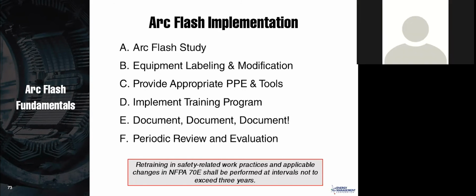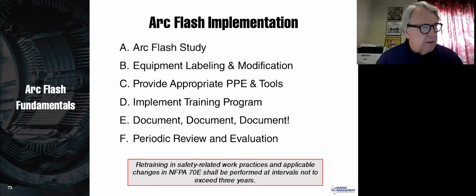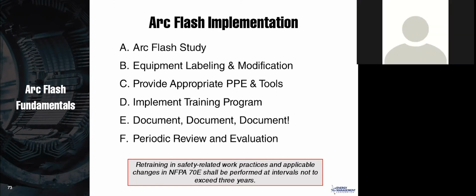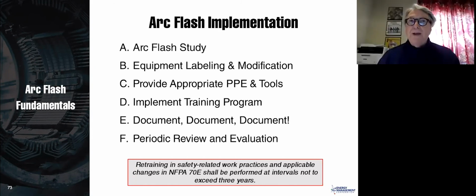Our first question that came in from David. Is there a minimum arc flash rating in which you don't have to label? Say that again, in which you don't have to what? In which you don't have to label. Oh, yeah, the answer is no. It used to be that a 125 kVA exemption would allow you to put on generic labels, but that's gone now. So basically, you have a switchboard, a panel board, what have you. It doesn't matter what the calories are. You must have a label.